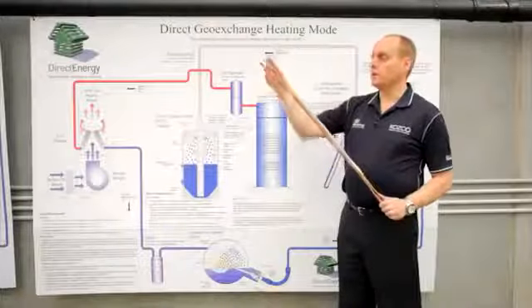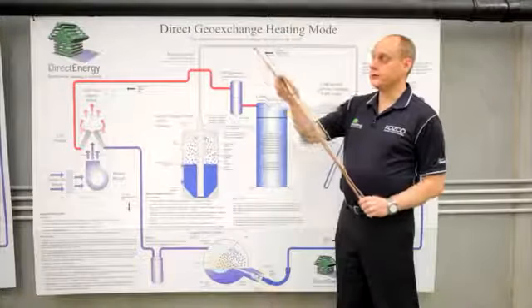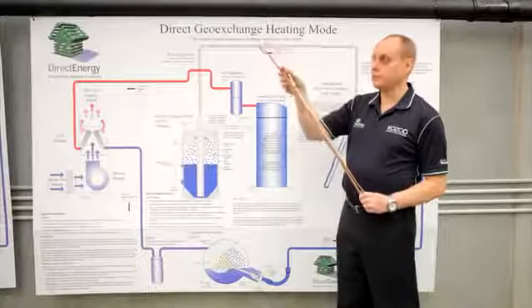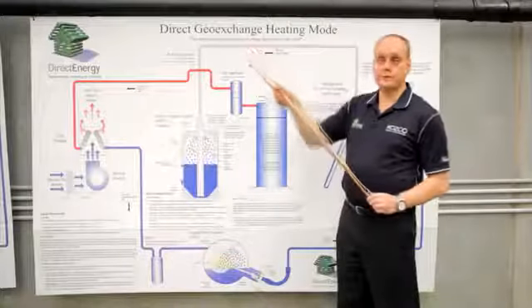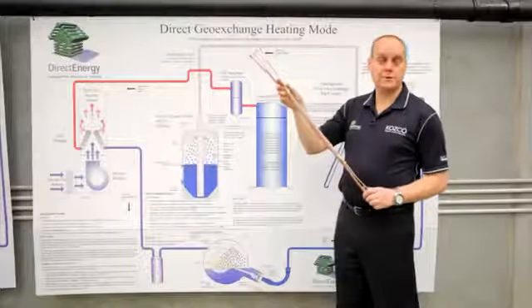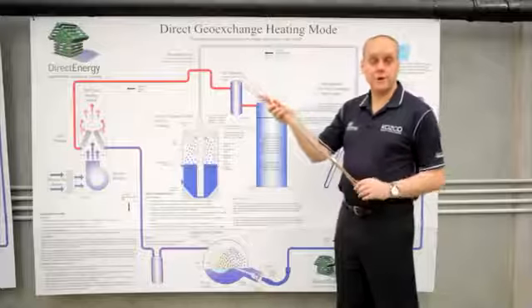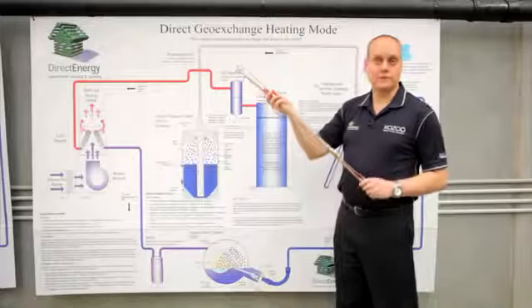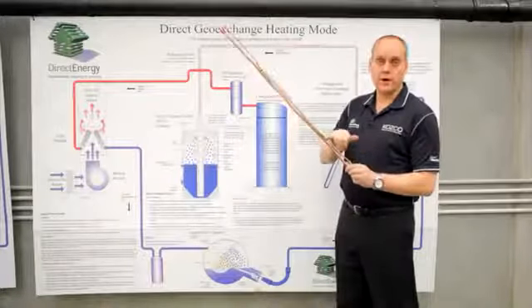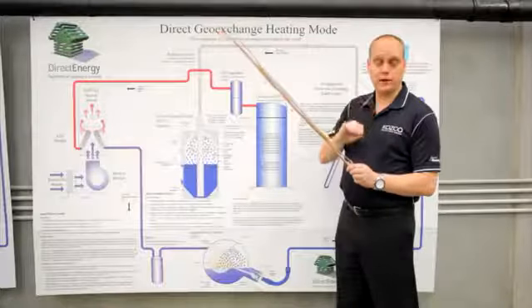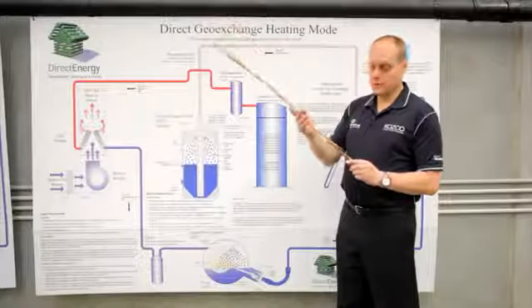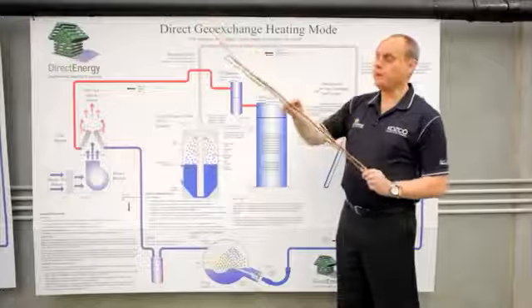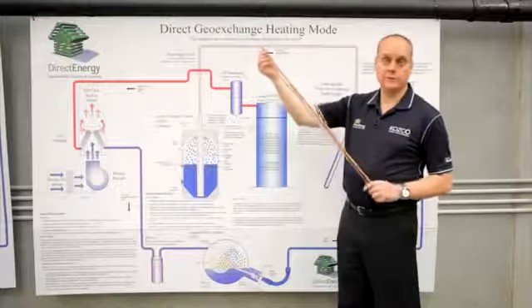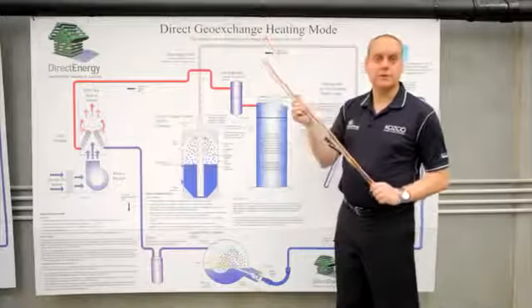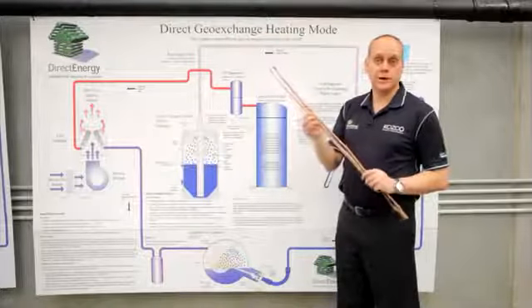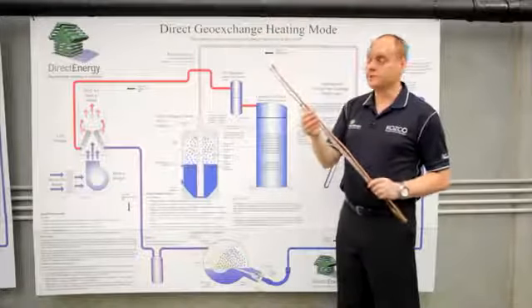So in heating mode, the liquid side of the refrigeration cycle is coming down inside the liquid loop into the ground. So we've got refrigerant that is in a liquid state at perhaps minus 10 degrees Celsius, going down here in Victoria into 15 to 17 degree ground. That warm ground temperature is going to be providing warmth into the refrigerant, warming it up and allowing it to evaporate off and come back up to the heat pump in a vapour state where it's compressed, made hot and used for air or water heating applications.